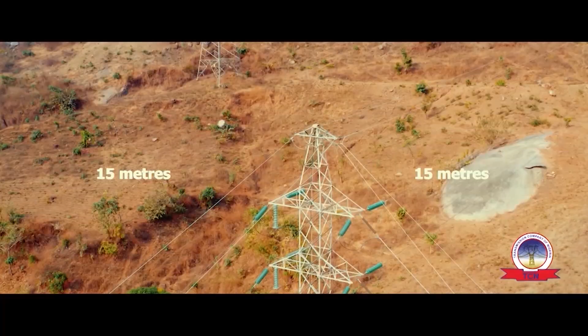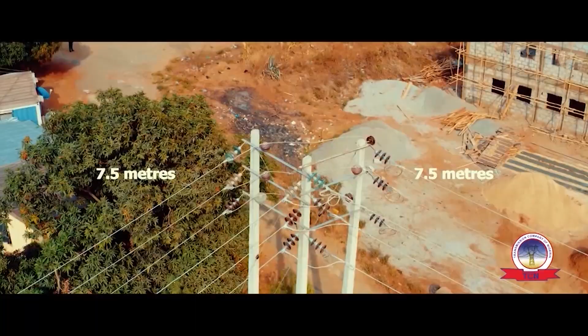Safety compliance simply means that before erecting any structure around any electricity tower or line, there are safety distances you must adhere to. These safety distances are 25 meters on both sides of the tower for a 330 kV line, 15 meters on both sides for a 132 kV line, and 7.5 meters on both sides for a 33/11 kV line. These stipulated safety distance instructions are what we call right of way. If these simple, basic safety distances are adhered to, trust me, there will be less loss of property and lives resulting from cut transmission lines.